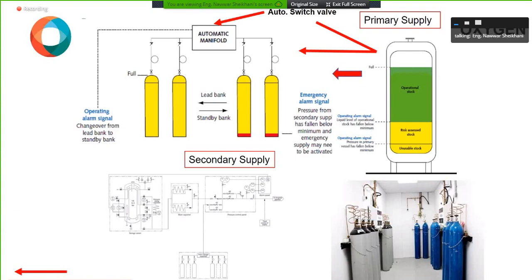Why automatic? Because we don't depend on a human to open the valve or the lever, or maybe he forgot to open it, like what happened in a certain hospital. In the last 6-7 years, we had 2 painful incidents in medical gas. One was related to the unavailability of an automatic switch between the manifold and the primary source. The other one was related to cross connection.